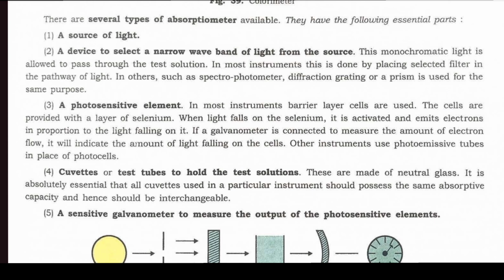तीसरा, यह photosensitive element. In most instruments, barrier layer cells are used. The cells are provided with a layer of selenium. When light falls on selenium, it is activated and emits electrons in proportion to the light falling on it. If a galvanometer is connected to measure the amount of electron flow, it will indicate the amount of light falling on the cells. Other instruments use photoemissive tubes in the place of photocells.